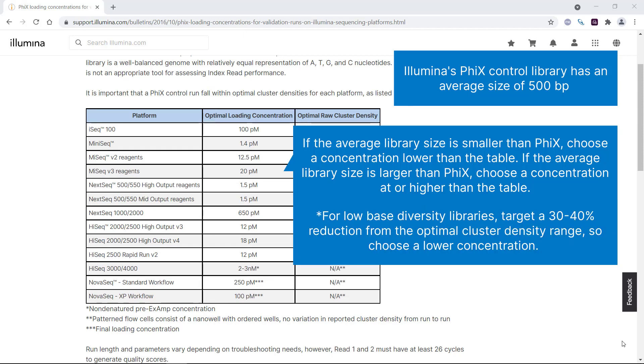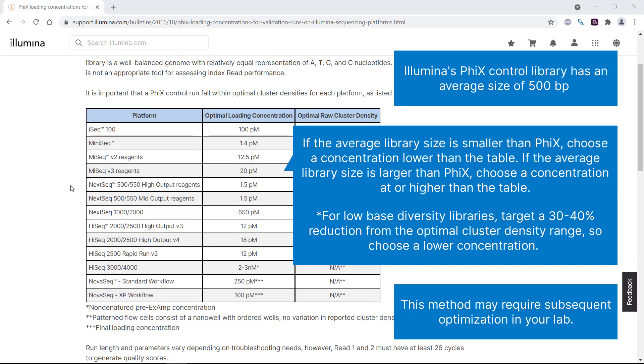Note that if we're sequencing a low base diversity library, Illumina recommends targeting a 30-40% reduction from the optimal cluster density range, so choose a lower concentration. This method may require subsequent optimization as every library type can have different clustering efficiency.